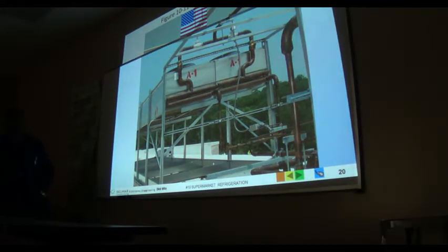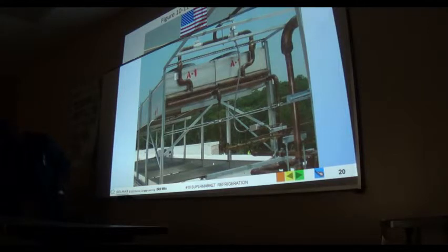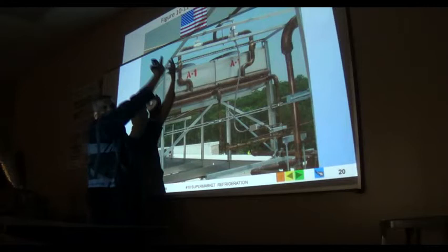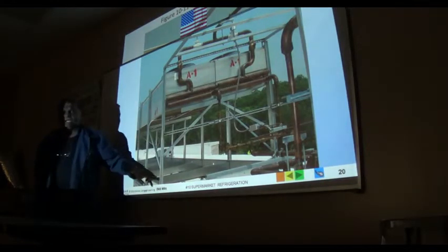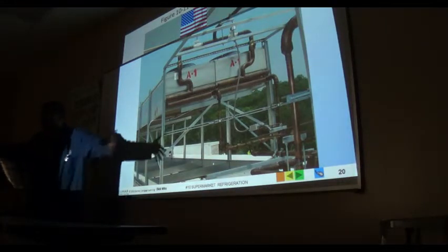I did think we mentioned towers, right? And I did mention those over there. This tower is a condensing tower, and actually this doesn't have water going to it. It's an air-cooled condenser. It has fans up here. No water. This sucks air from below, and out the top. That's why it's raised. Even the smaller ones are about knee high from the floor, so that air goes in.